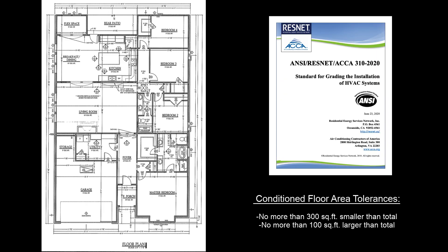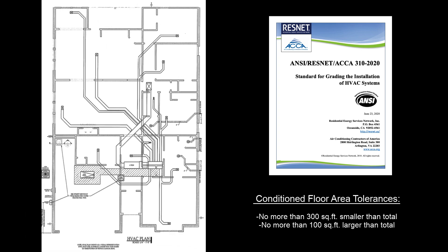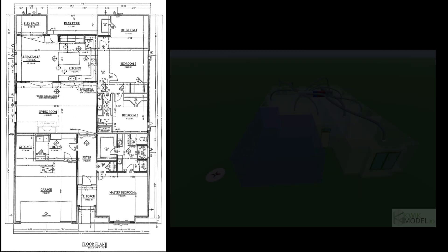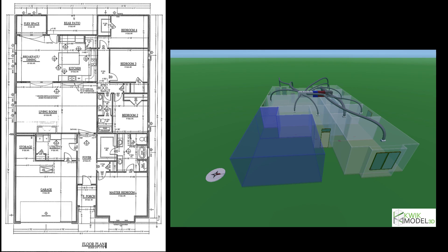Make sure the plans you use reflect the correct final layout of the house. Make sure that the conditioned floor area, window areas, and all of the exterior surface areas taken from the plans are reflective of the actual house. For new homes, Standard 310 allows for tolerances of 300 square feet smaller and 100 square feet larger than the current HVAC design, although it should be easy to be more accurate than this. Make sure you perform your load calculations for the actual orientation of the home. For new construction, the designer will have rotated the orientation around the compass and decided whether different size equipment was needed for different orientations. Typically, they will size equipment for the worst case orientation.